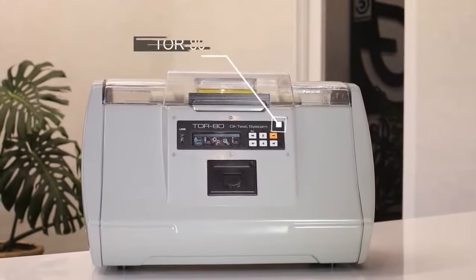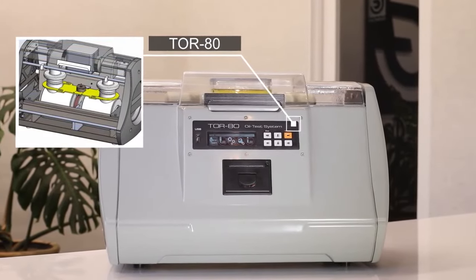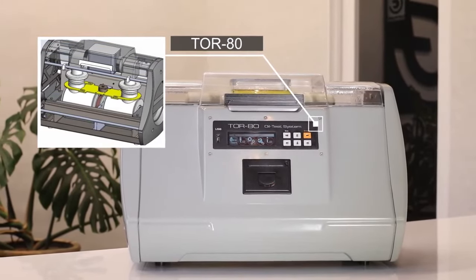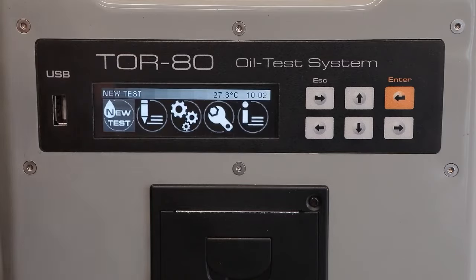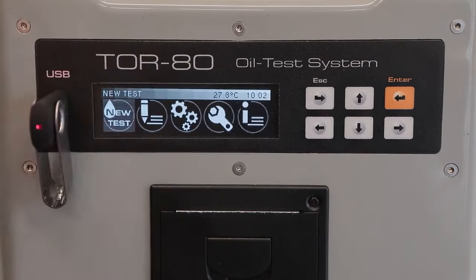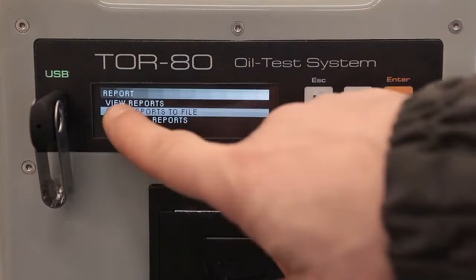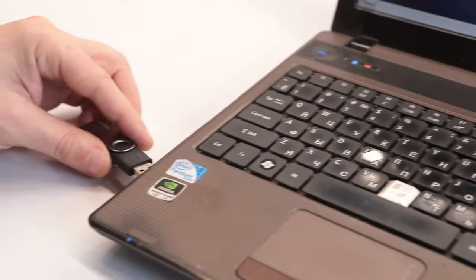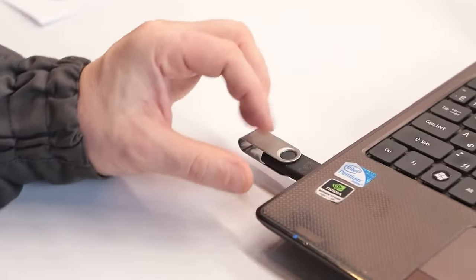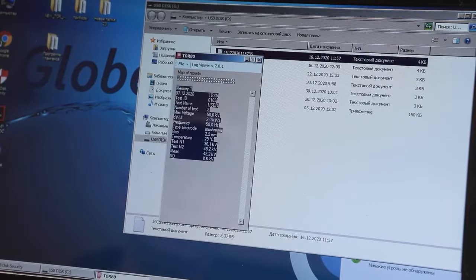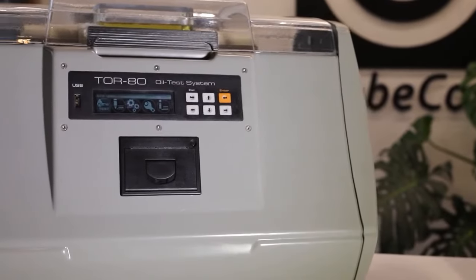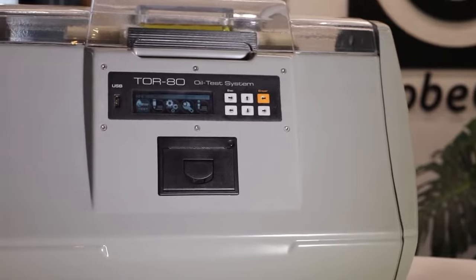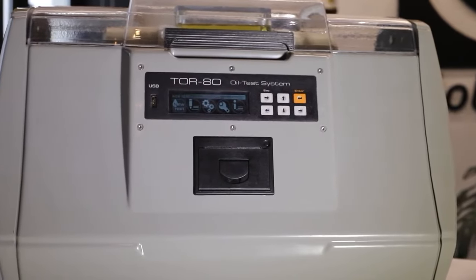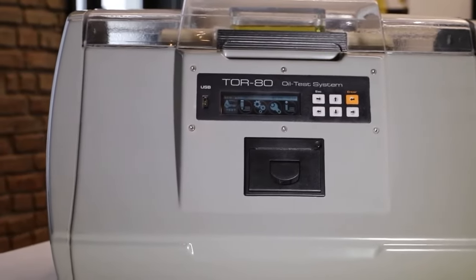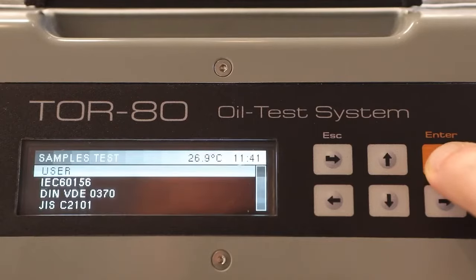At the same time, the device remains convenient and practical. If necessary, the measurement results can be printed out on the built-in thermal printer or copied to a flash drive from the internal non-volatile memory and to a computer for subsequent statistical processing and visualization. If it is necessary to determine the breakdown voltage using a non-standard procedure, the user can do so by specifying individual settings. Let's consider them in detail.